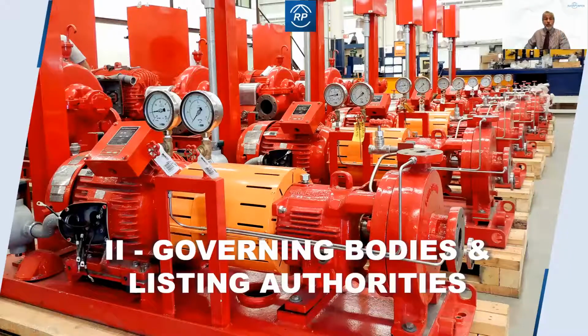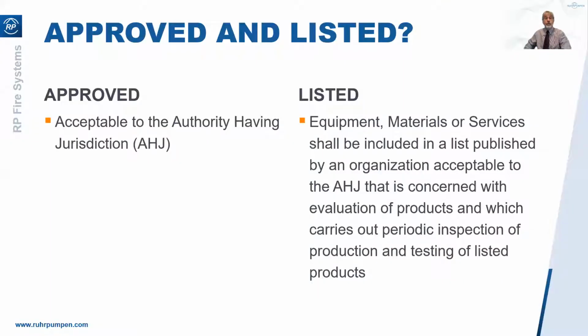Now, NFPA-20 requires that fire pumps be approved, which means acceptable to the authority having jurisdiction, whatever that might be. If it's an oil and gas installation, it might well be the principal oil and gas company, Esso or Shell or Exxon or Mobil. It also requires that they be listed by an organization acceptable to the authority having jurisdiction. And that would be an organization that is concerned with the evaluation of products and which carries out periodic inspection of production and testing of the listed products.